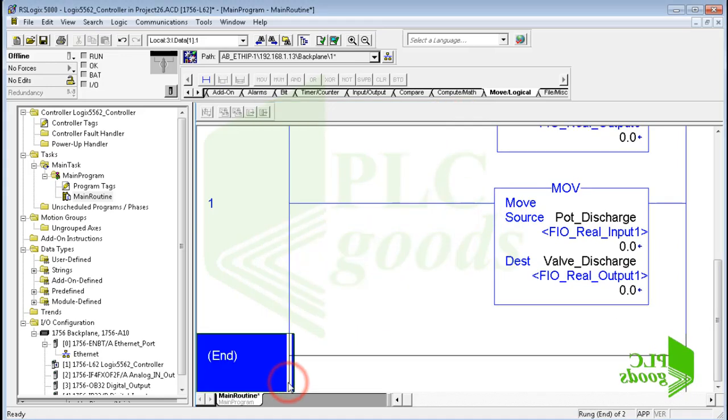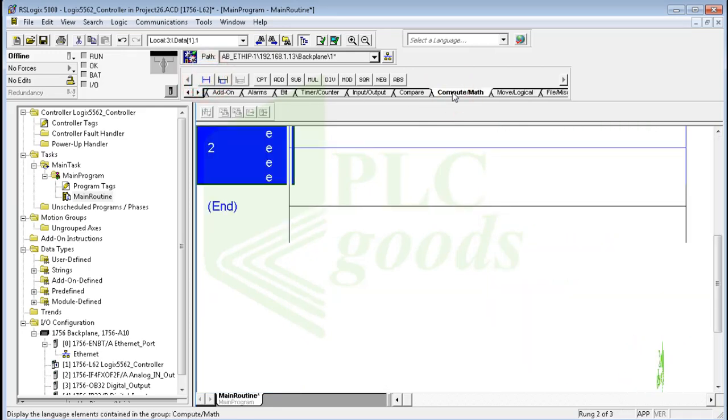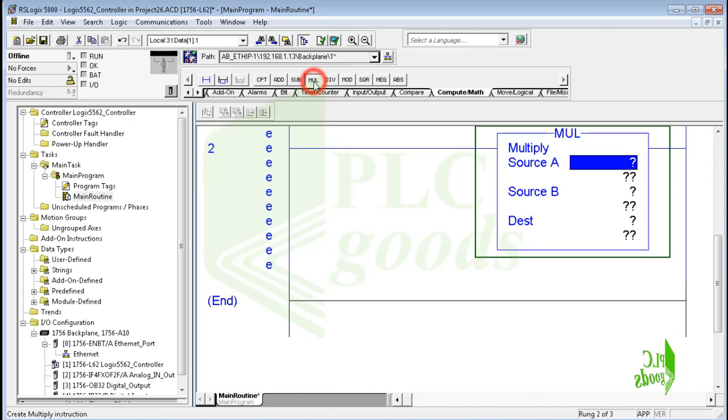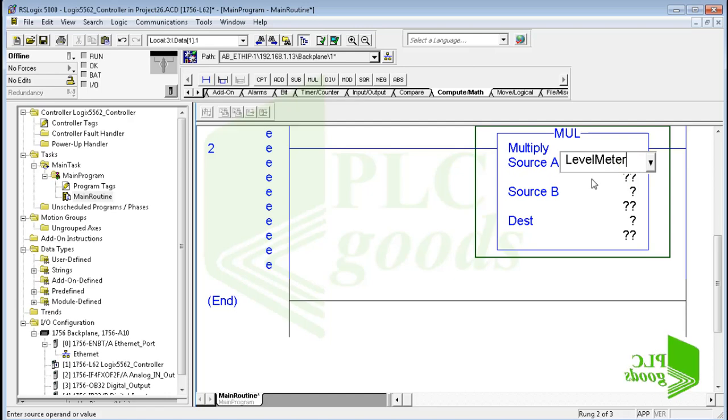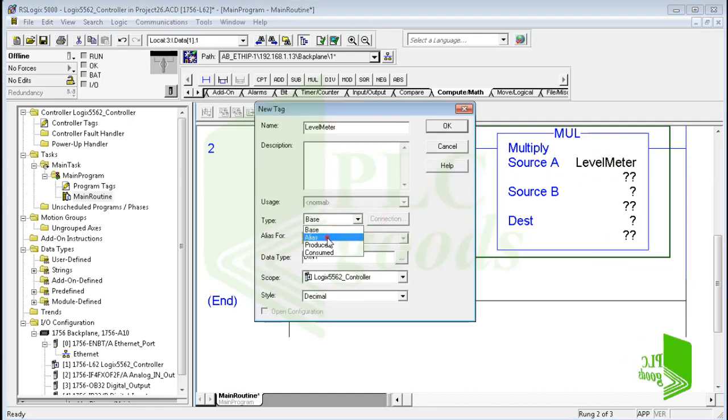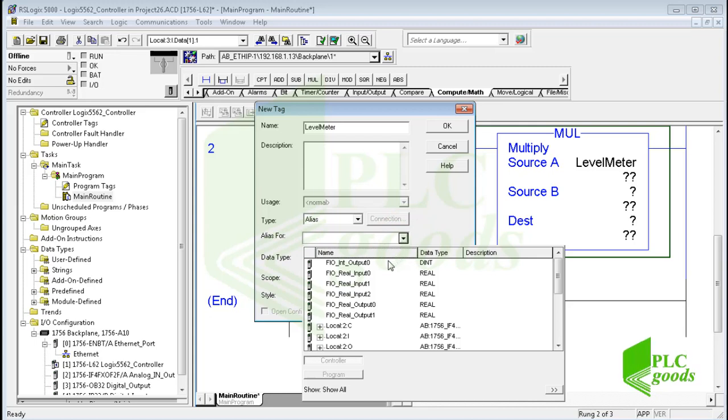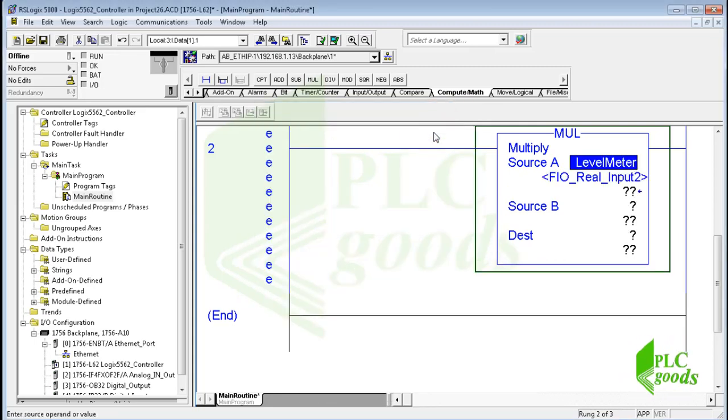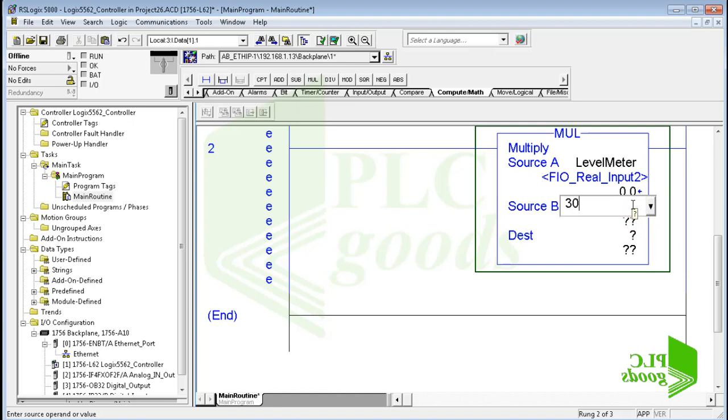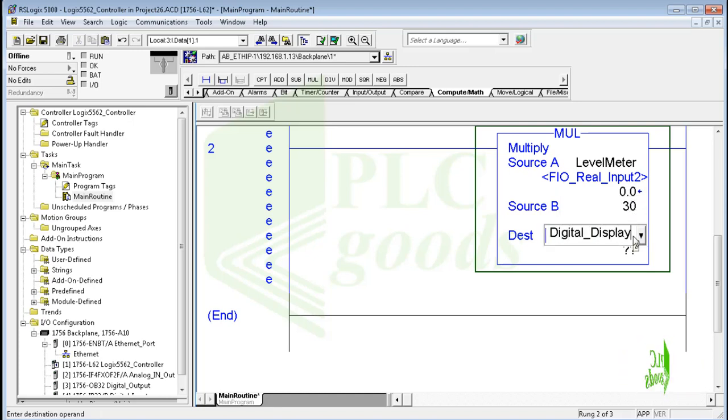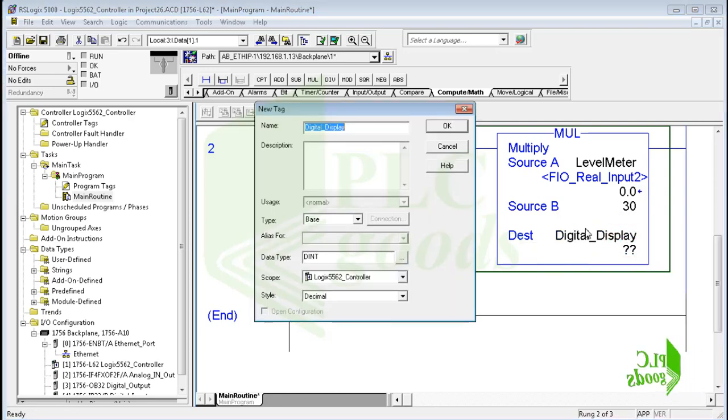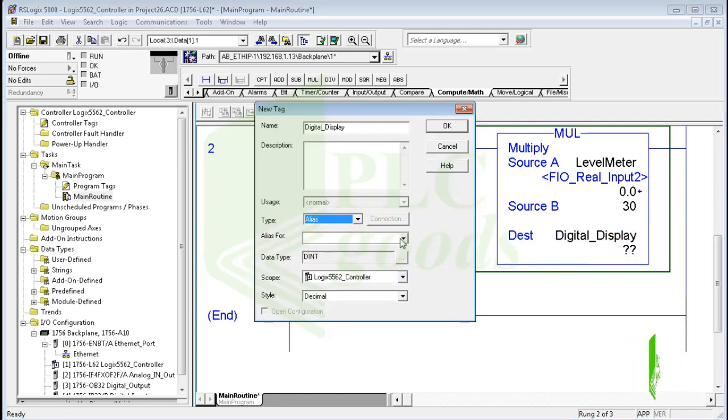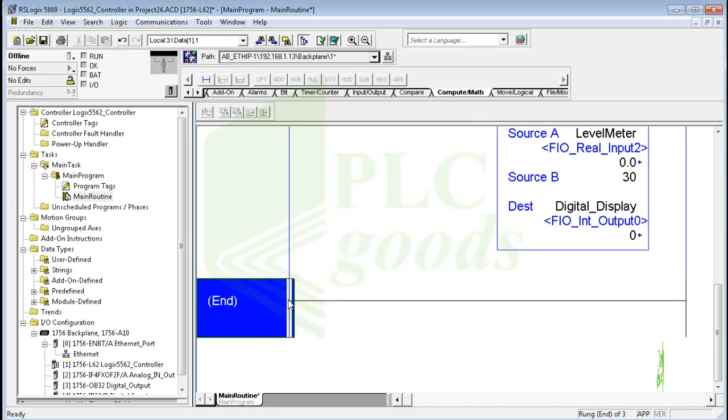Alright, let's continue programming. The level meter sends a voltage between 0 and 10 to my PLC. So I need to multiply it by 30 and send the result to the digital display output. Now let me insert an analog alarm instruction.